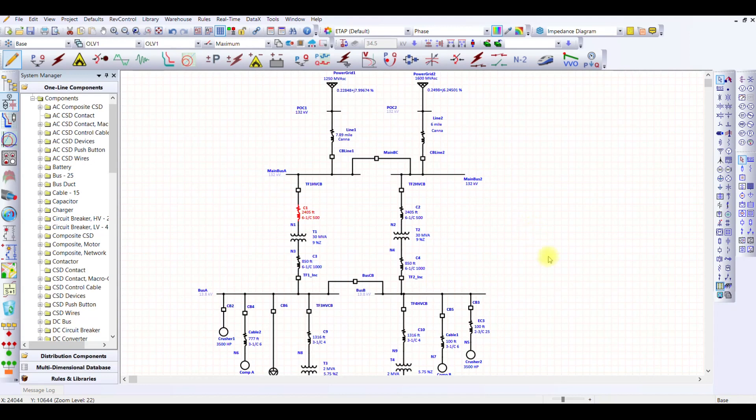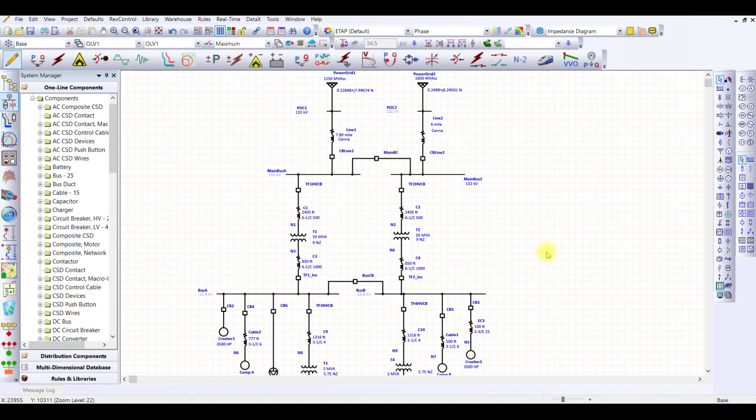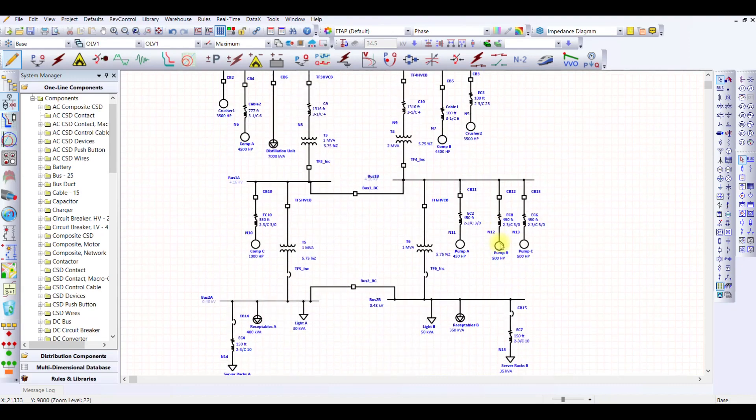This means that although we do not have modeled a power grid for the single line to ground fault, we can get single line to ground fault with respect to transmission line data. Same goes for the cable data. If I go to cable data and impedance, we see here we have a zero sequence different than positive sequence. So it means that we will be able to get different short circuit level for unbalanced fault because we have modeled it properly. But for now, as we discussed that in an industrial network, three phase short circuit is far more worse as compared to single line to ground fault, so we will be emphasizing more on three phase short circuit.